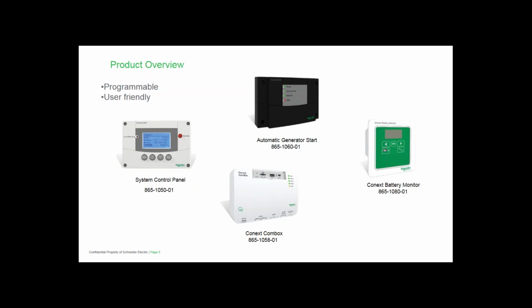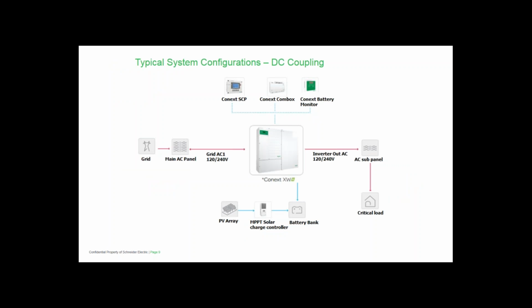Before we focus in on the ComBox, let's talk about a couple of typical system configurations. Here we see a diagram of a typical grid-connected DC coupled system. When DC coupling, the PV supplies the charge controller, which in turn regulates to the battery and protects from overcharging. The XW will then take that energy to prioritize the battery power over the grid power to satisfy your AC load demand. And if you're set up to sell, then any excess power being generated that your subpanel does not consume will be exported back towards your main panel and then ultimately to the grid.